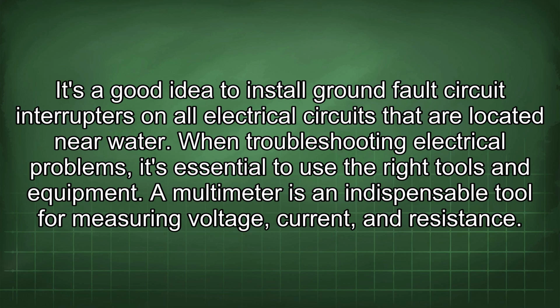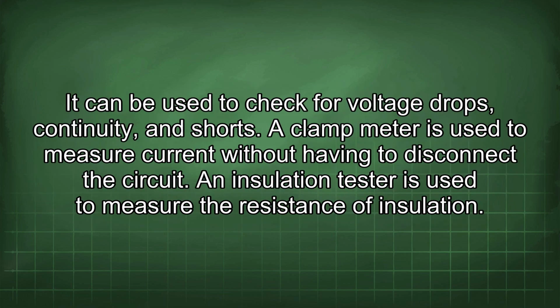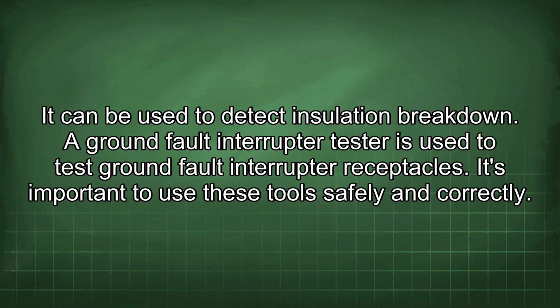When troubleshooting electrical problems, it's essential to use the right tools and equipment. A multimeter is an indispensable tool for measuring voltage, current, and resistance. It can be used to check for voltage drops, continuity, and shorts. A clamp meter is used to measure current without having to disconnect the circuit. An insulation tester is used to measure the resistance of insulation. It can be used to detect insulation breakdown. The ground fault interrupter tester is used to test ground fault interrupter receptacles.